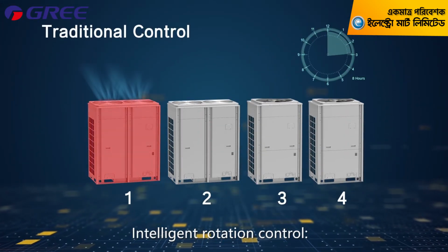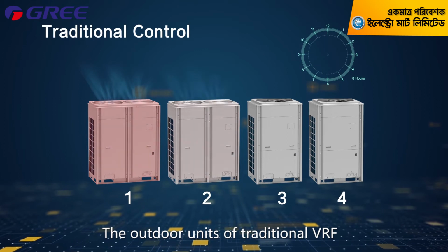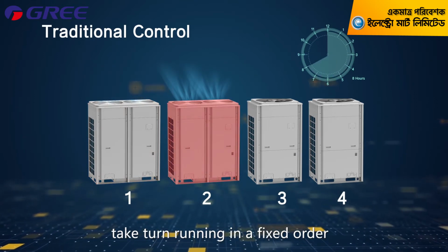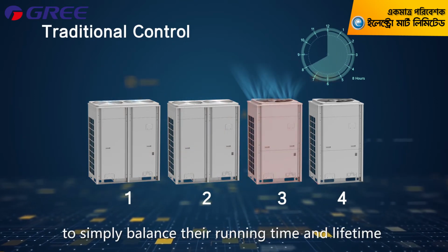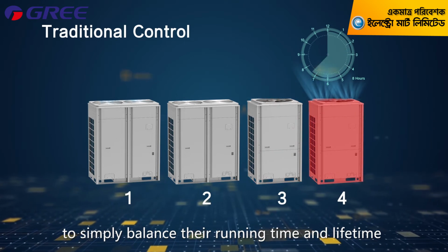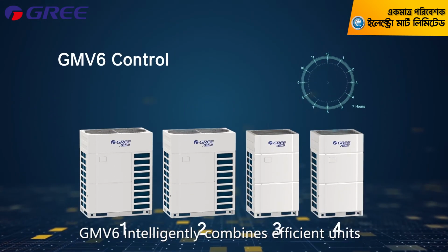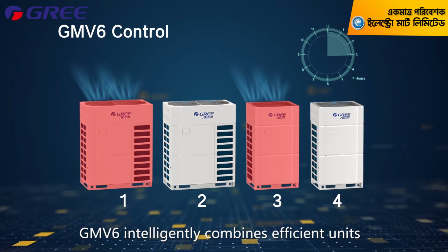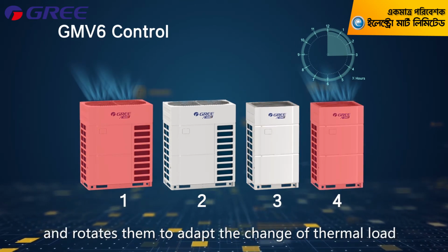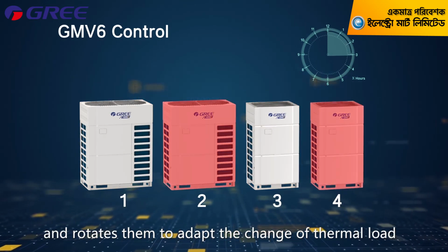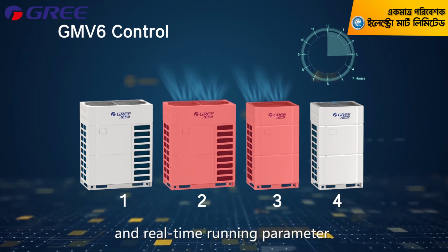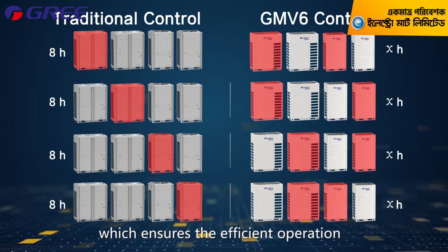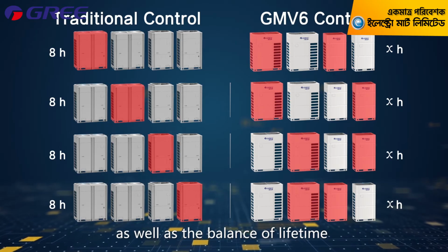Intelligent rotation control: the outdoor units of traditional VRF take turns running in a fixed order to simply balance their running time and lifetime. GMV6 intelligently combines efficient units and rotates them to adapt to the change of thermal load and real-time running parameters, which ensures efficient operation as well as the balance of lifetime.